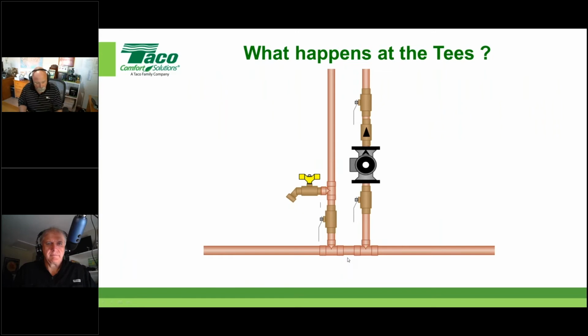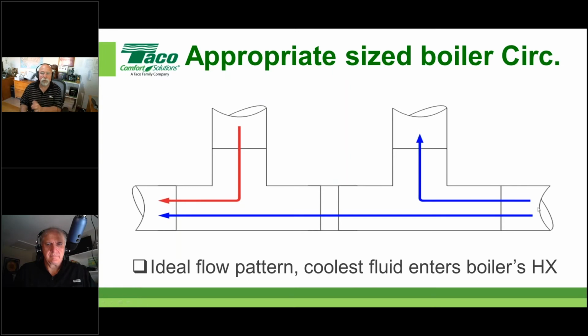So let's go in and focus on these two T's right here. I'm going to blow this up and have you visualize what's happening at that point. Here it is, a cutaway view of those two T's. The appropriate size boiler circ is going to give you exactly what we want here. We want the coolest water coming back to the boiler and therefore getting the boiler to condense like it's supposed to. Then the boiler water is heated up, comes back out, blends at that blending point that John was talking about earlier, and goes out to the system. So this gets a right hand thumbs up. That's really what we want to happen ideally.